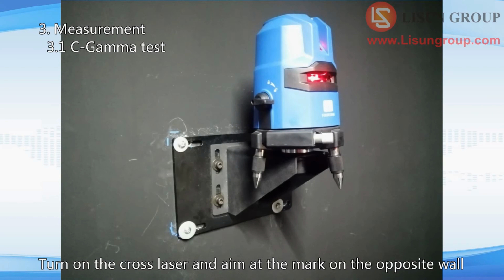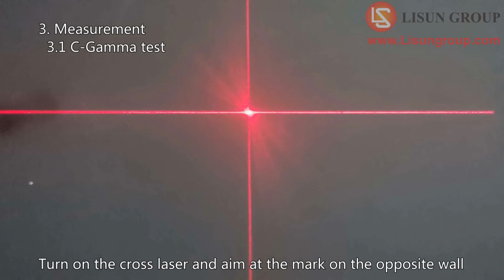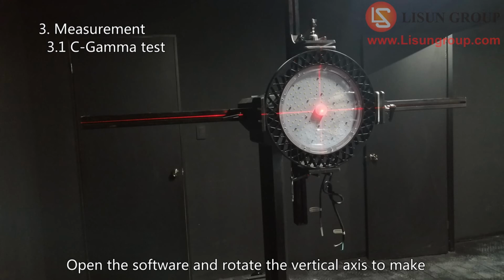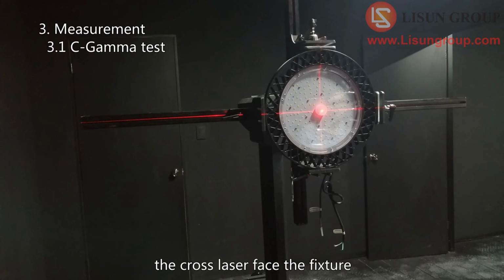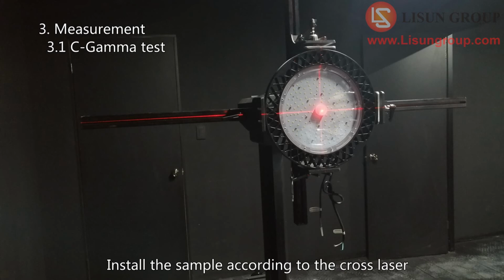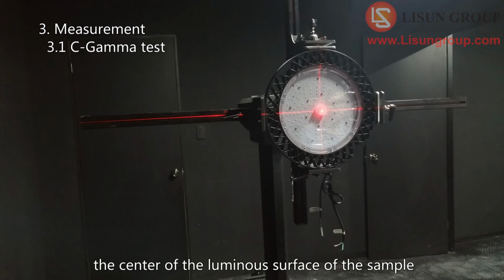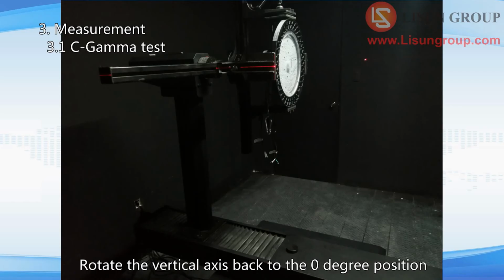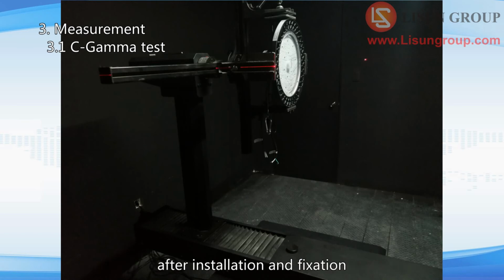Turn on the cross laser and aim at the mark on the opposite wall. Open the software and rotate the vertical axis to make the cross laser face the fixture. Install the sample according to the cross laser. Make sure that the cross laser center point is at the center of the luminous surface of the sample. Rotate the vertical axis back to the 0 degree position after installation and fixation.